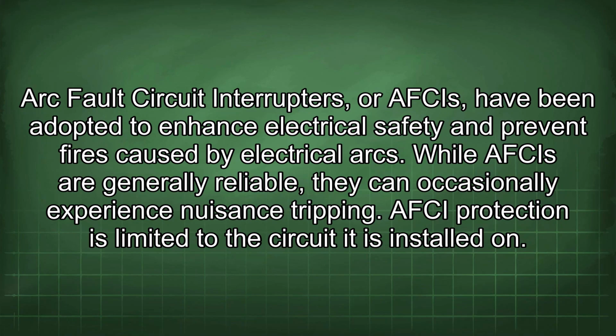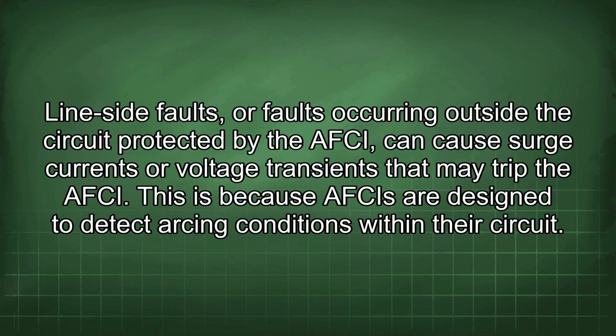Arc fault circuit interrupters, or AFCIs, have been adopted to enhance electrical safety and prevent fires caused by electrical arcs. While AFCIs are generally reliable, they can occasionally experience nuisance tripping. AFCI protection is limited to the circuit it is installed on. Line-side faults, or faults occurring outside the circuit protected by the AFCI, can cause surge currents or voltage transients that may trip the AFCI. This is because AFCIs are designed to detect arcing conditions within their circuit.